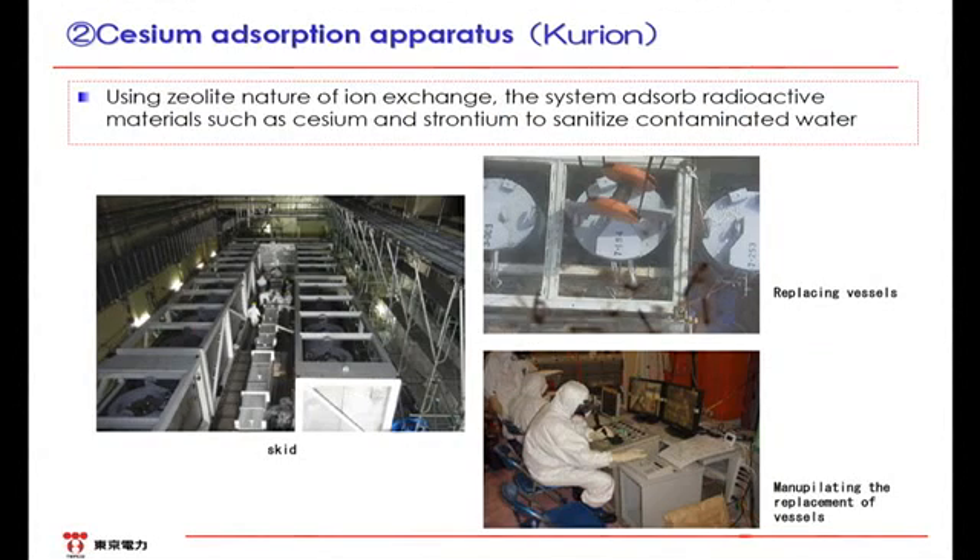Next is the Kurion separator, which is the cesium adsorption apparatus. Cylindrical vessels are located in the box called skid. Zeolite is in the vessels. When the water goes through zeolite, cesium contained in the water is adsorbed, and thus the water is purified. Generally, the current decontamination index, DF, is 10 to the fifth power, which means that cesium is adsorbed to the level that the concentration of the outgoing water is approximately 1/100,000 of that of the incoming water. The cesium adsorption apparatus is replaced once every two to three days. Since the radiation dose at the surface is high, this work is done remotely. The staff operates a joystick to hoist a vessel and move it to the storage area.